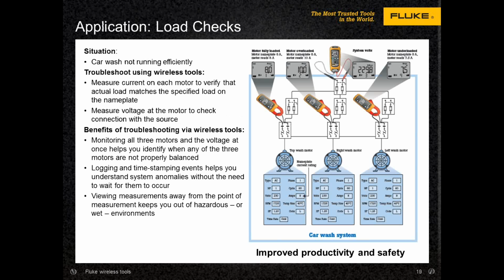Here's another, we touched on that. Here's an example of doing a load check on a car wash system, which is actually 3 different motors. So you can look at this over a period of time. You can monitor all 3 motors at the same time. You can look at the changes during the course of a day. You can gather that information. You can identify whether the motors are running well together, or whether it's easy to see overcurrents, undercurrents, or what the nominal load should be according to the nameplate ratings. Now I noticed on looking at some of these modules, the current, you have inrush.